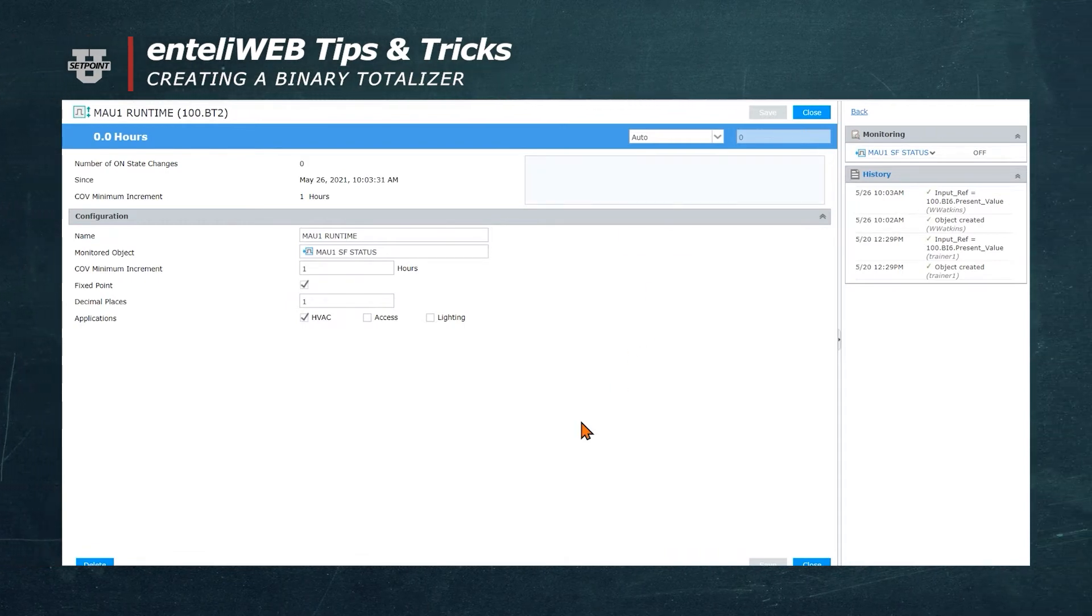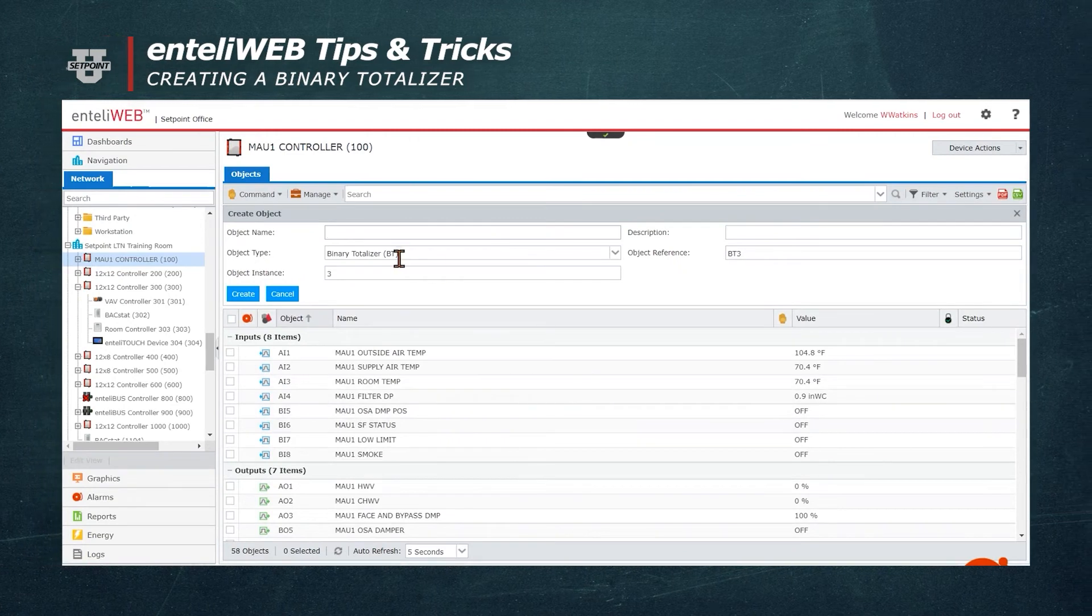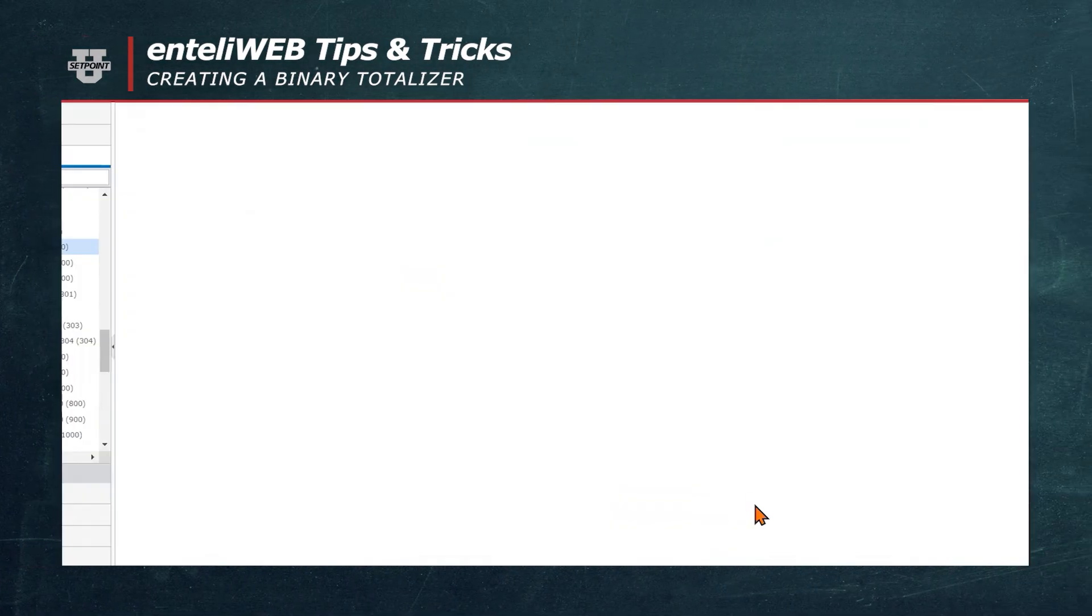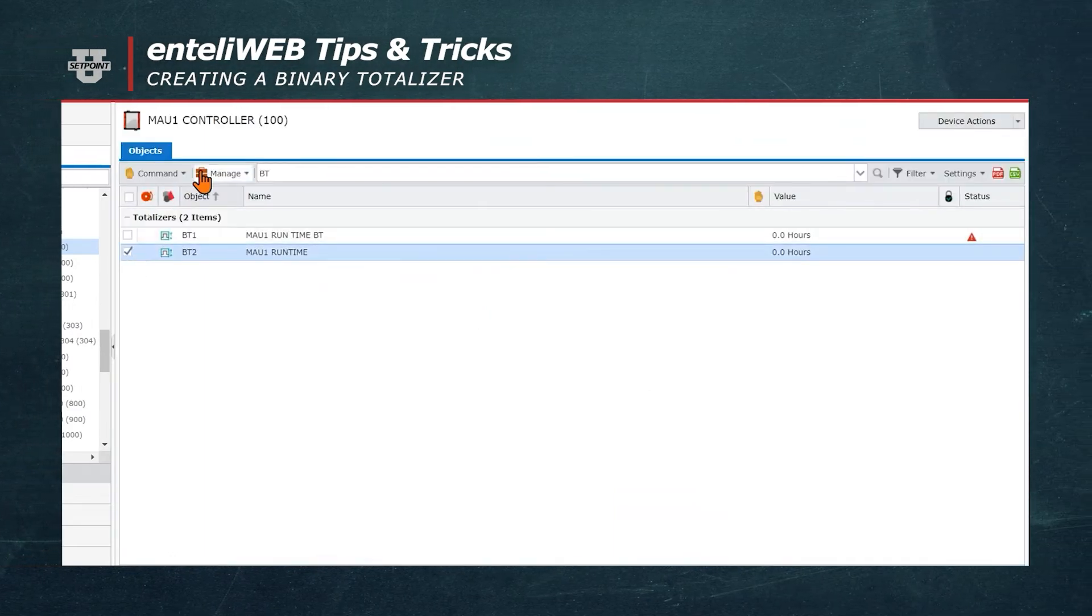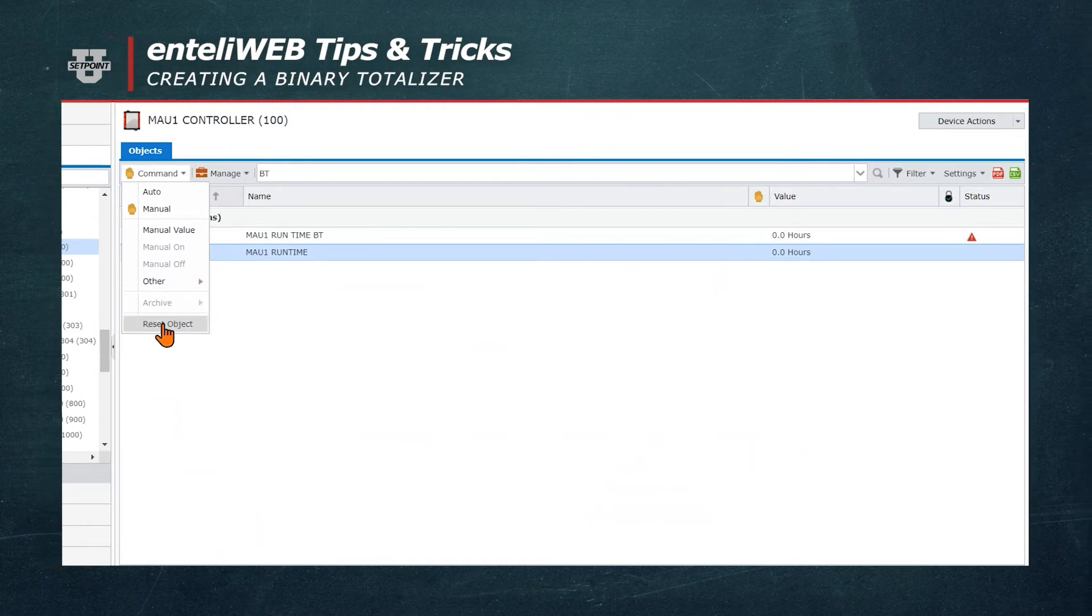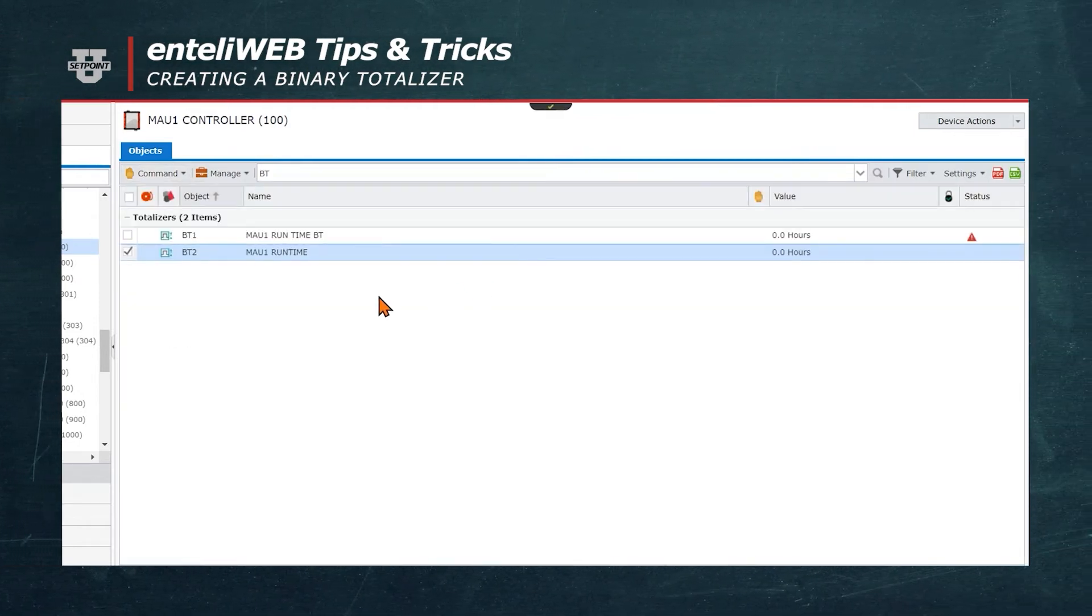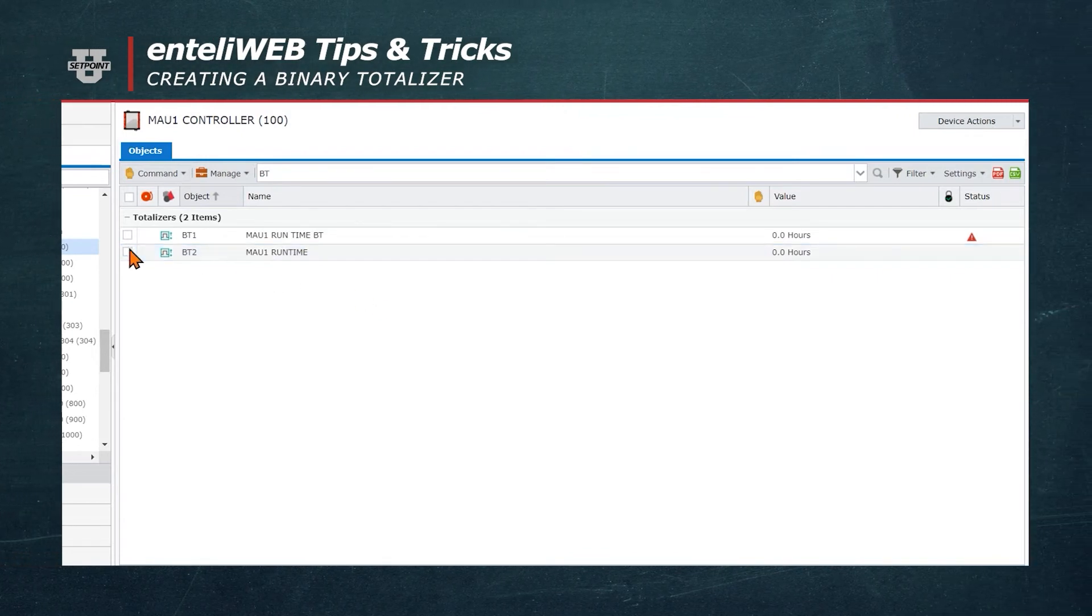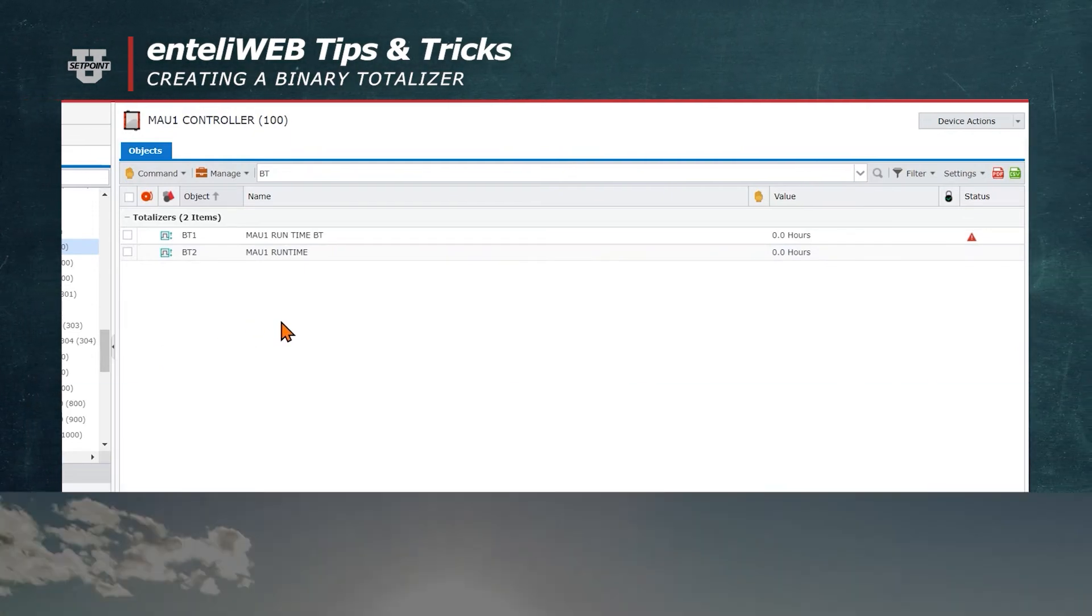If you want to reset this value, you can come back over to enteliWEB and type BT into the search bar. We can select the Binary Totalizer that we just built, and we'll go up to Command and hit Reset Object. That will put the runtime back to zero. If there was any runtime showing, it would start calculating it again, and it would start tracking the runtime from the beginning.